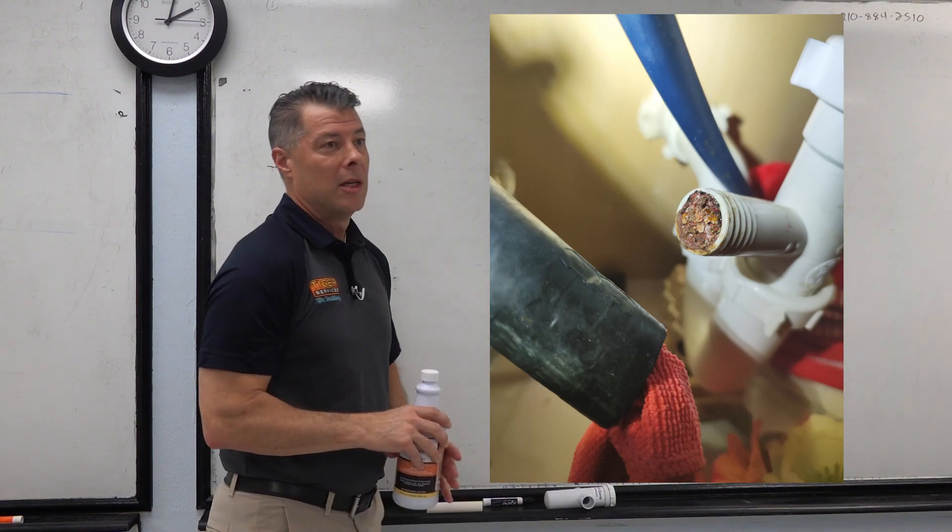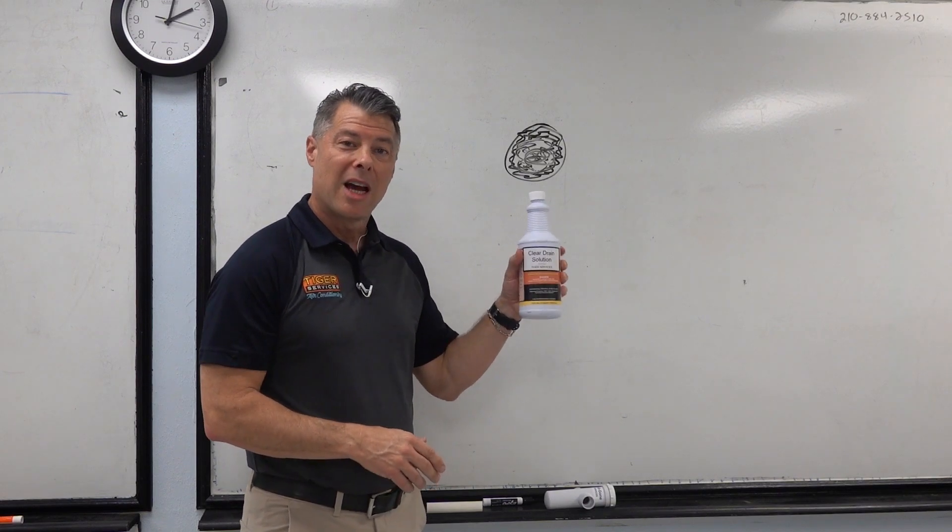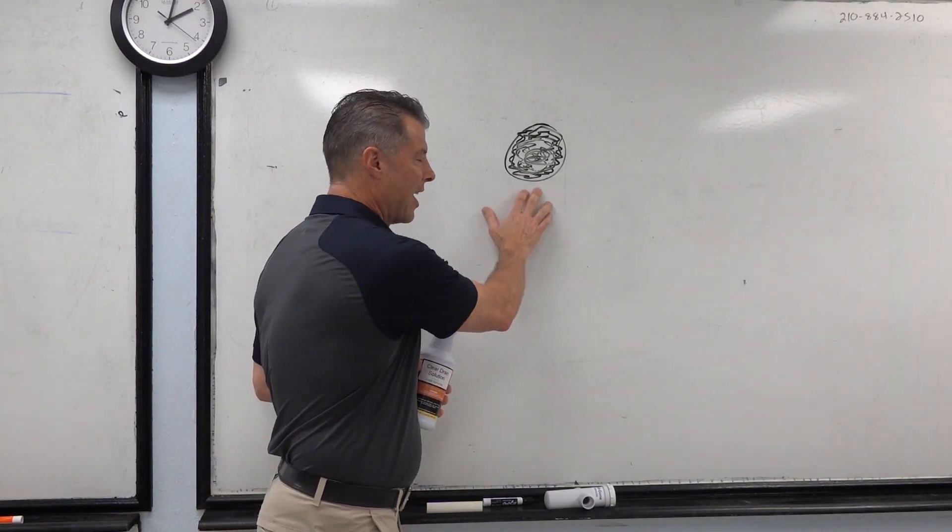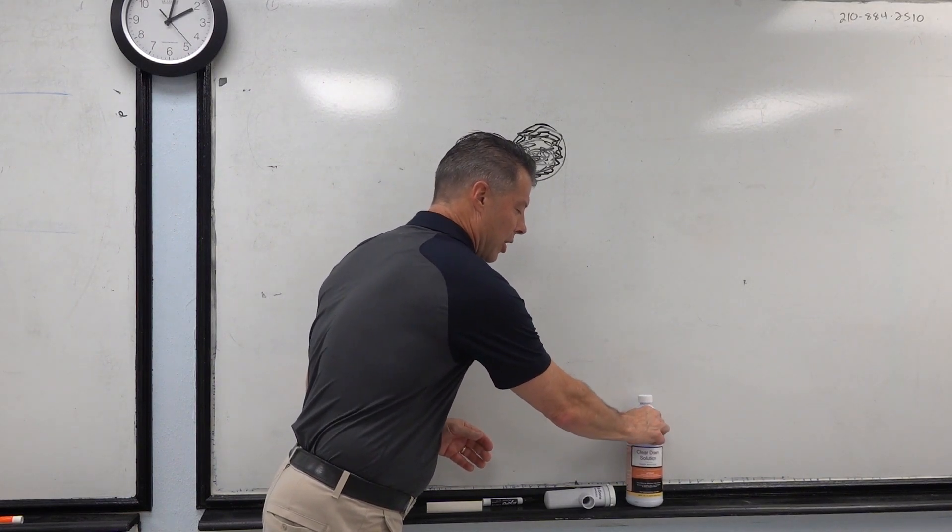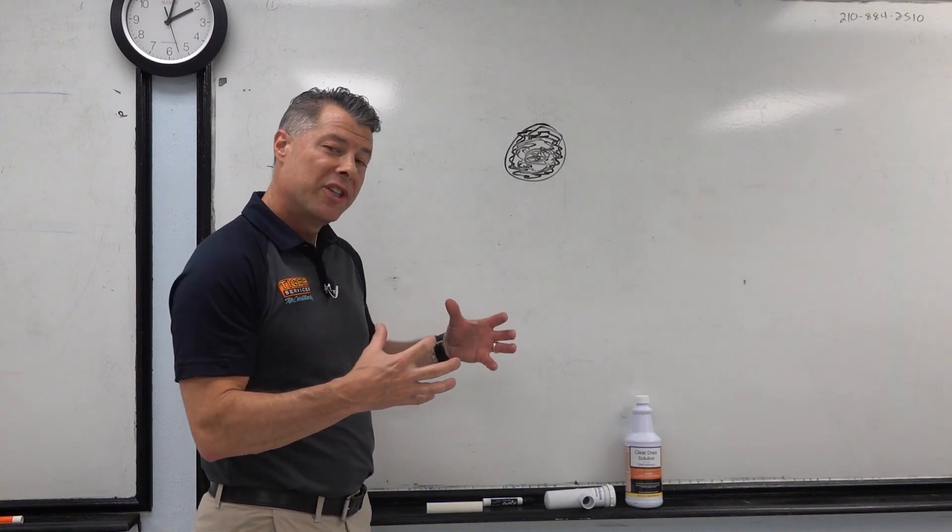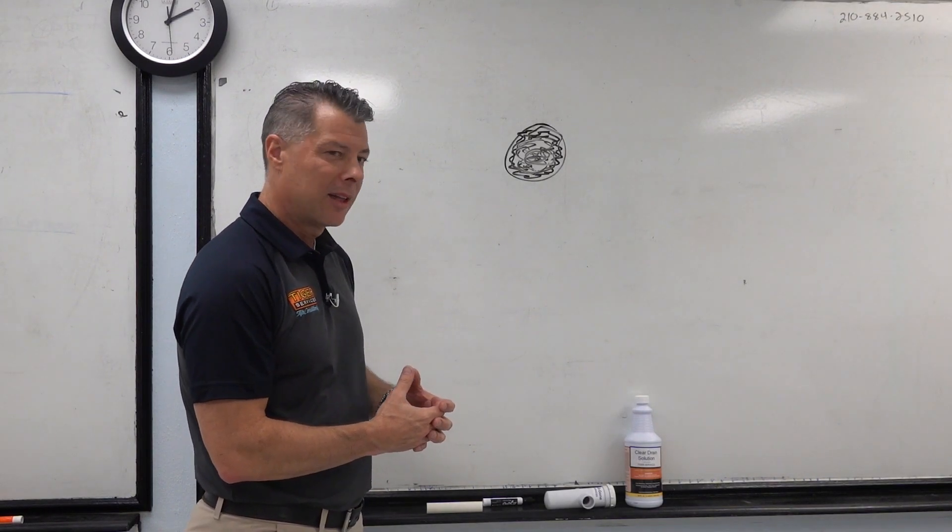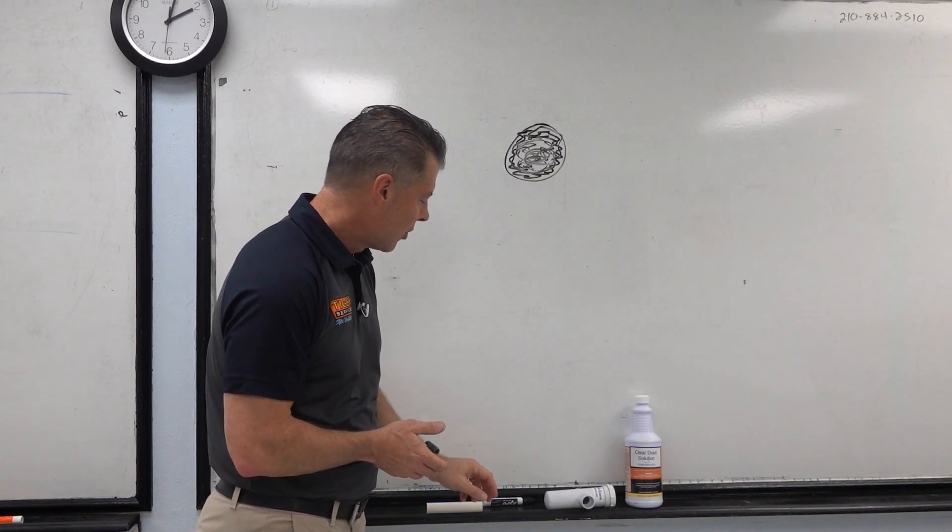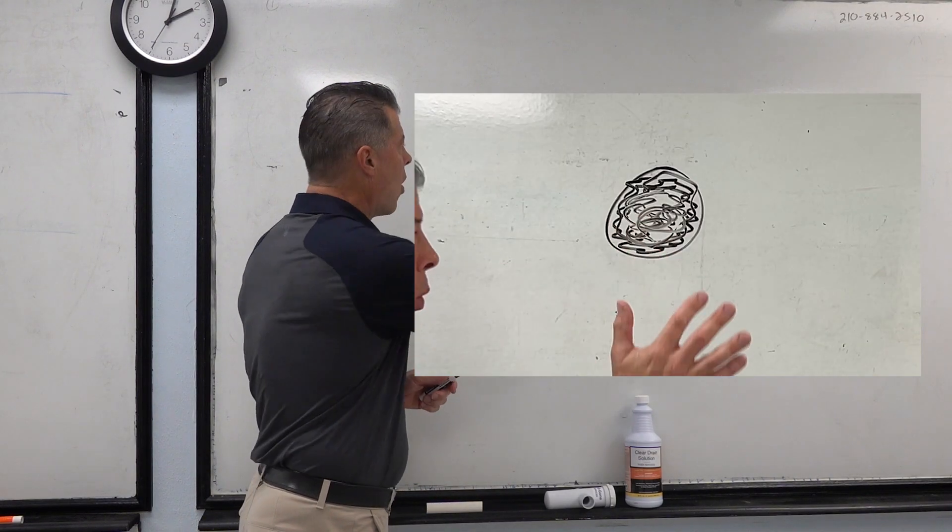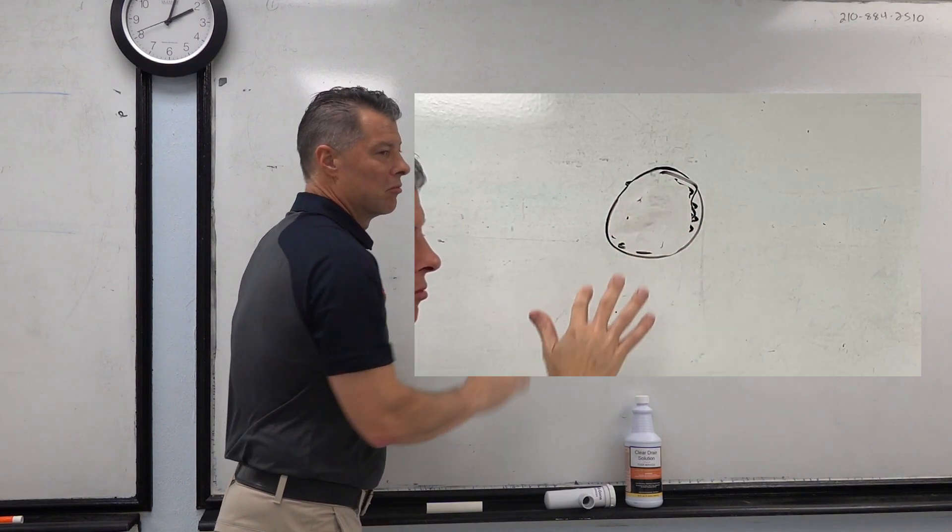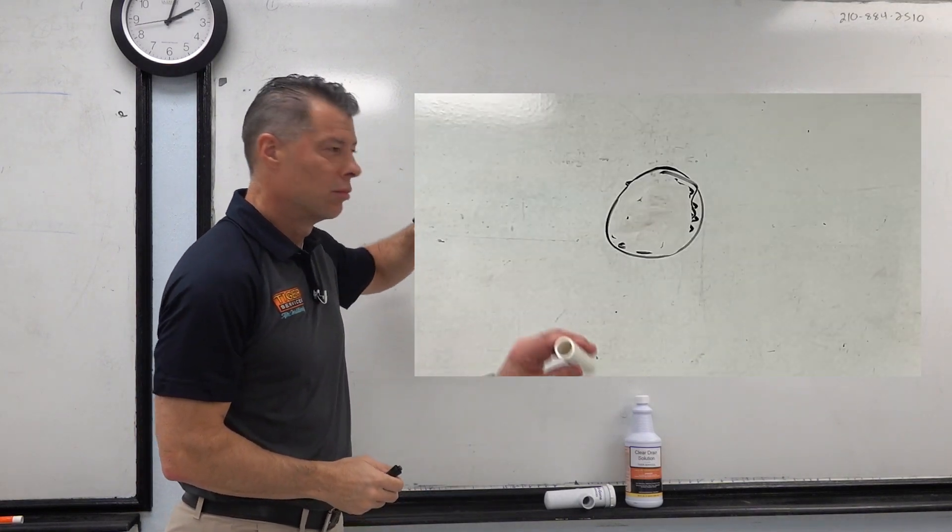So what we recommend is a product called CDS. It's a chemical that's made directly for condensate lines. It's not going to hurt your indoor coil. So what we do is we pour it in the condensate line at your inside unit. We wait about 15 minutes. We pour water in it, about two gallons. And when we're done, it kind of looks like that.